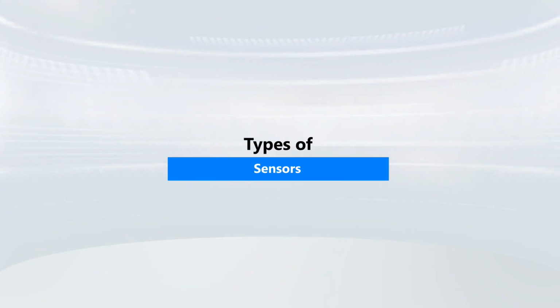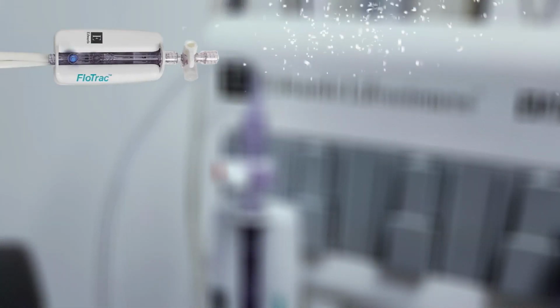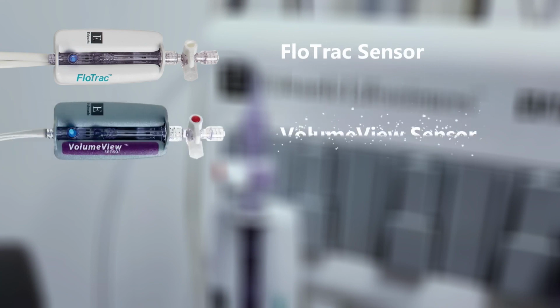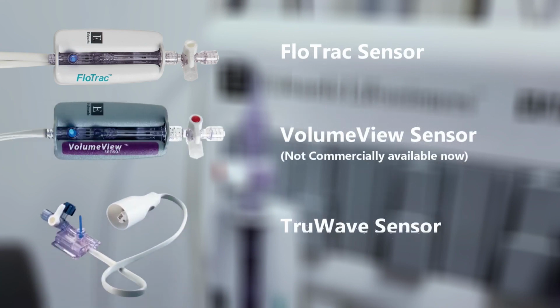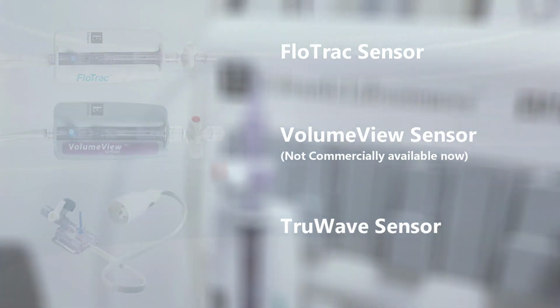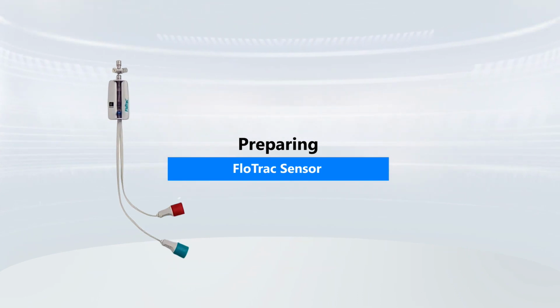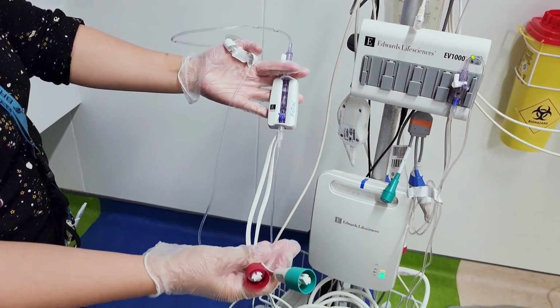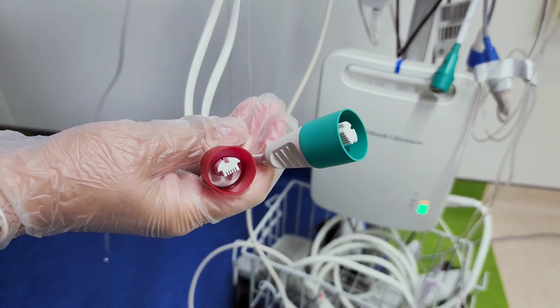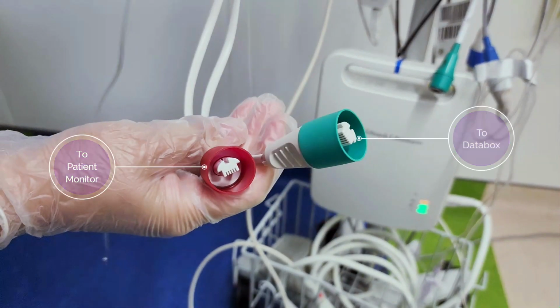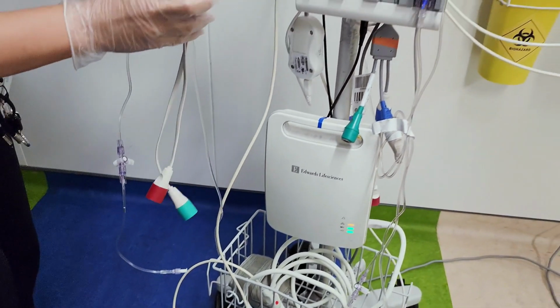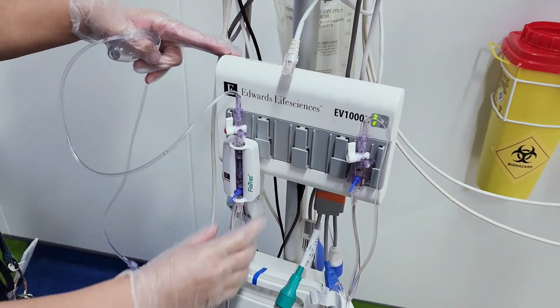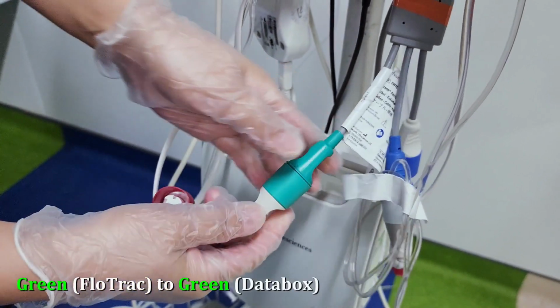For invasive hemodynamic monitoring, you'll need 3 basic sensor kits. These are the FloTrac sensor, which we'll be using for the arterial line connection, the VolumeView sensor, however it's not available, and the TruWave sensor for your central venous pressure connection. So the FloTrac sensor has 2 cable ends, color red and color green. The green one goes to the data box while the red one goes to the patient monitor. Then simply fix the FloTrac sensor to the Edwards data box and secure all the connections.